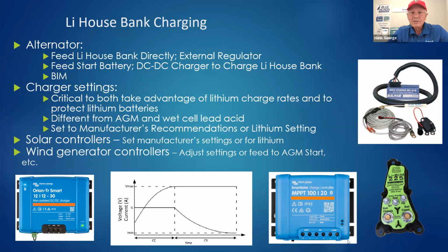When you do that, there are other factors to consider. One is protecting against a load dump, where the alternator has nowhere to send its power. The best solution is a fairly new device that came out last year from Balmar, and there's also a competing device from another company, called an alternator protection module, or APM - either the APM 12 or APM 24. You want to put that on every alternator feeding your lithium bank.